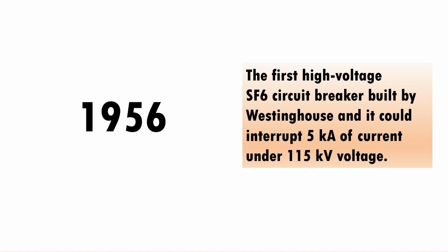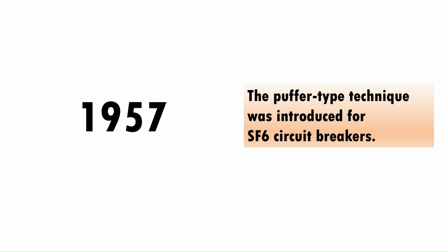In 1957, the puffer type technique was introduced for SF6 circuit breakers, where the relative movement of a piston and a cylinder linked to the moving part of the breaker contact is used to generate the pressure necessary to blast the arc via a nozzle. The nozzle is made of insulating material. In this technique, the pressure rise is obtained mainly by gas compression.